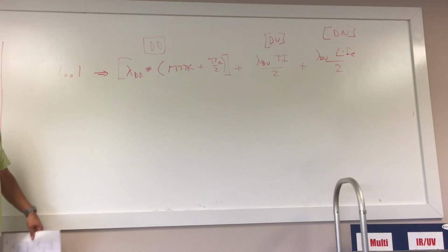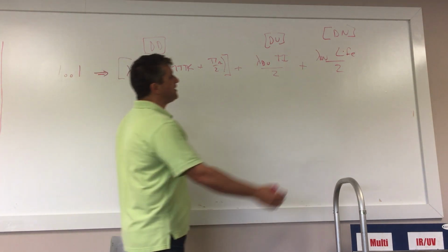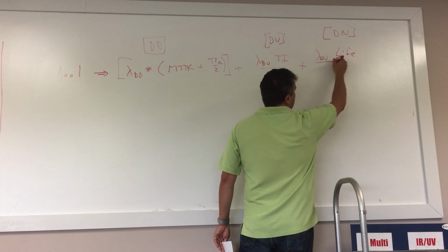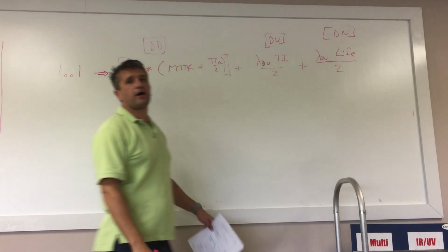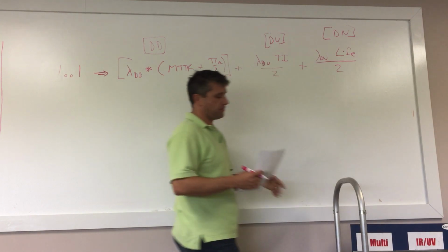Just some rough numbers. We generally expect for a smart transmitter to have about 99% manual proof test coverage and a valve system about 95% coverage. But lambda DN is real, and it's something that we need to account for in our calculations. And again, this is an unreliability.